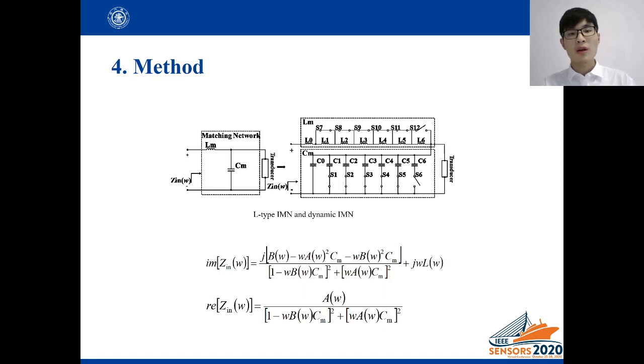According to the following equations, we can know the imaginary part depends on the Lm and Cm, while the real part only depends on the Cm. Therefore, the real part needs to be determined through Cm first, and then LM can be confirmed by adjusting the phase to zero.